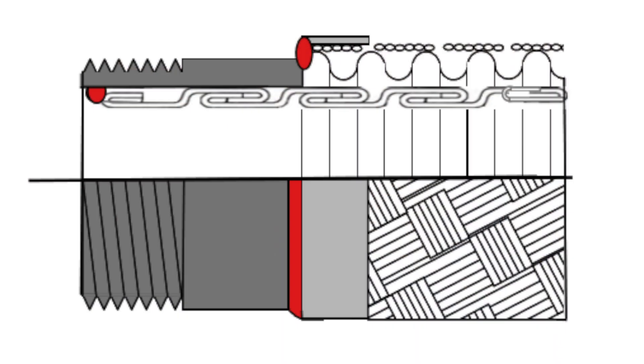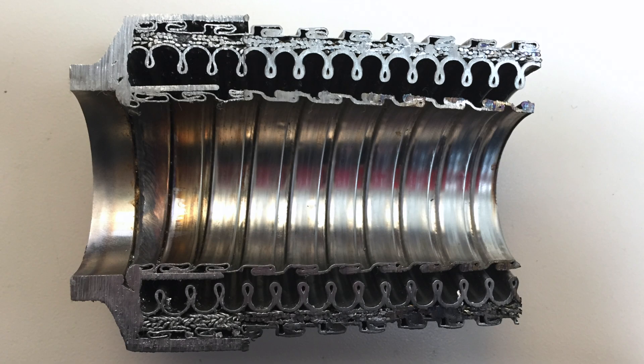There are several ways we can address this. One of the common ones is to add an interlocked liner. The interlocked liner smooths down the flow velocity so we don't have that turbulence. This protects the corrugations from excessive velocity. But interlocked hose inside as the liner can present other problems — it makes the assemblies heavier and it makes the construction a little more complicated.